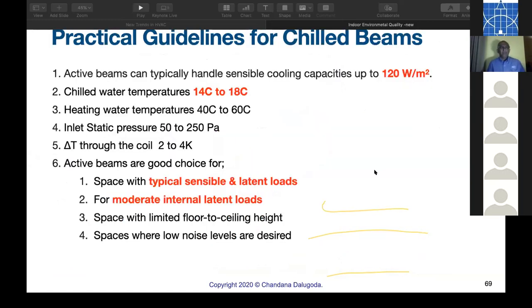Practical guide to chill beams. Active beams, 120 watts per square meter. Chill water temperature, 14 to 18. Heating water temperature, 40 to 60. Static pressure, 50 to 250. Delta T, 2 to 4K.